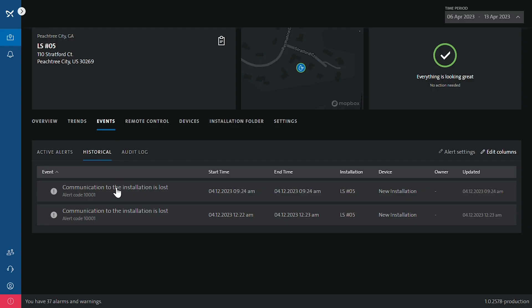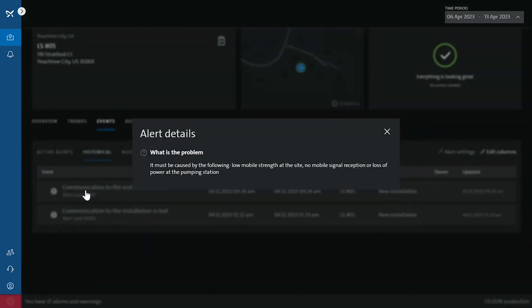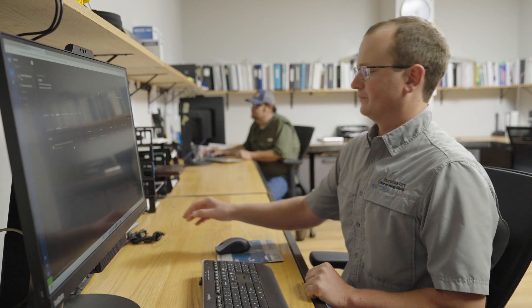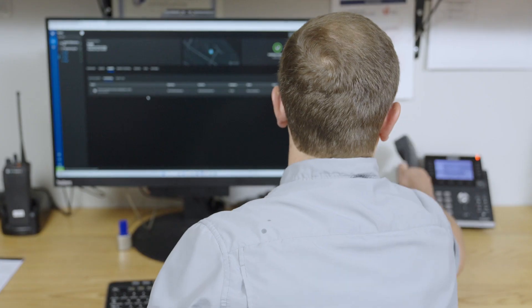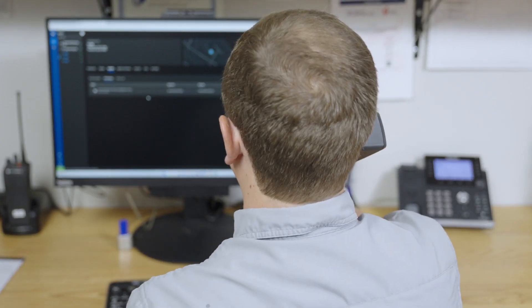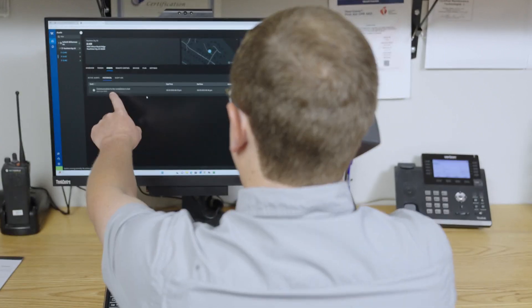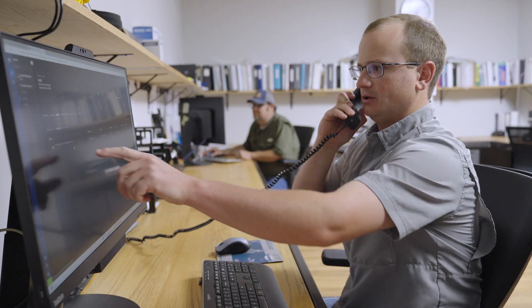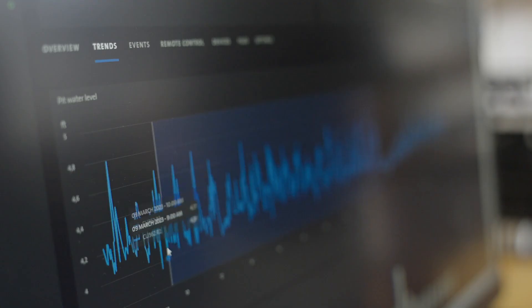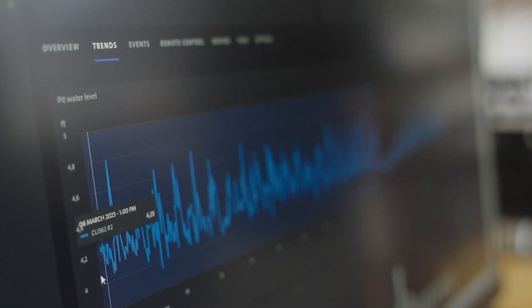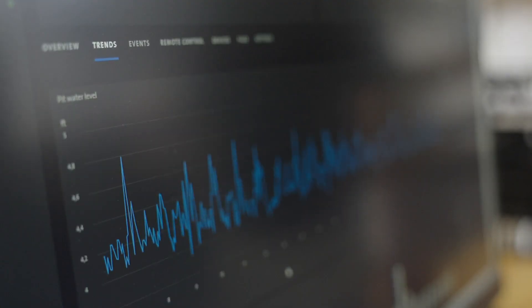We've experienced several situations where the Grundfos remote system has alerted a customer to a pump that was about to fail. They would call us up and we can log on to the system with them and then explain to them, 'Okay, look at this trend here. You can see here that your flow is going down, your amp draw is going up, your run times are increasing.